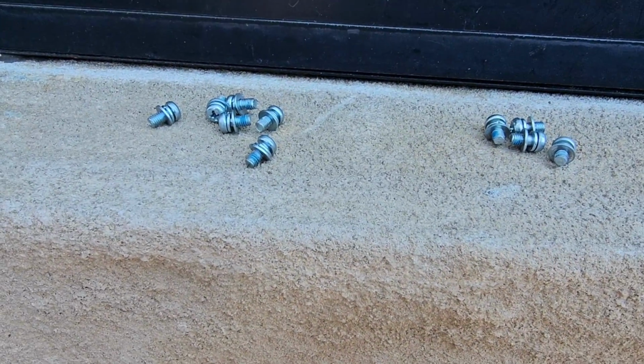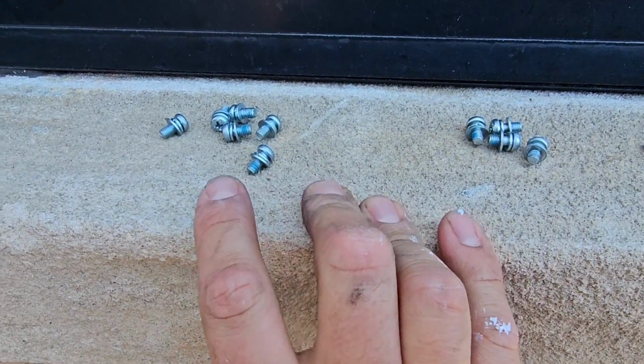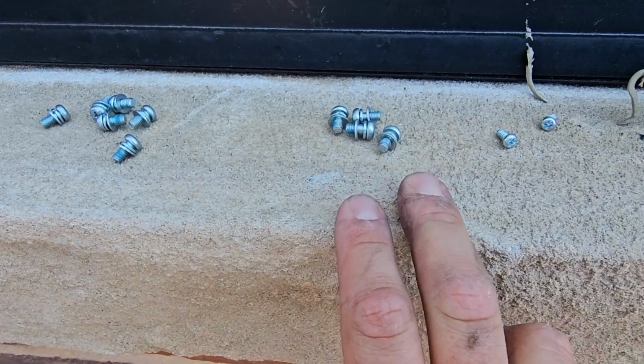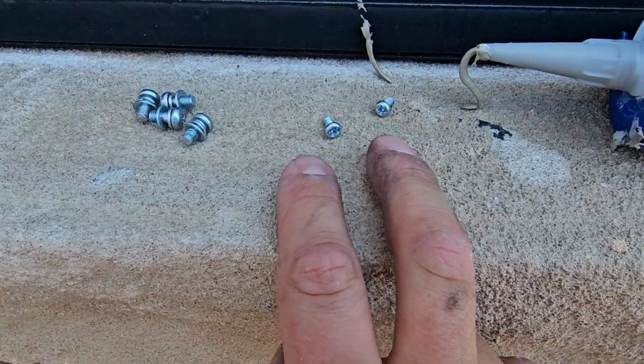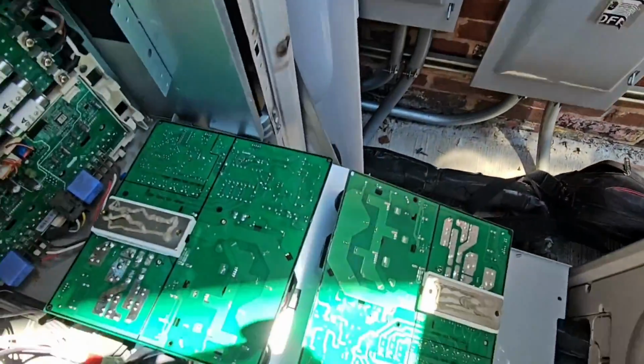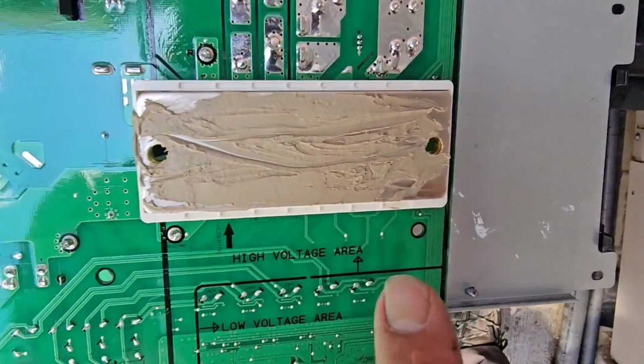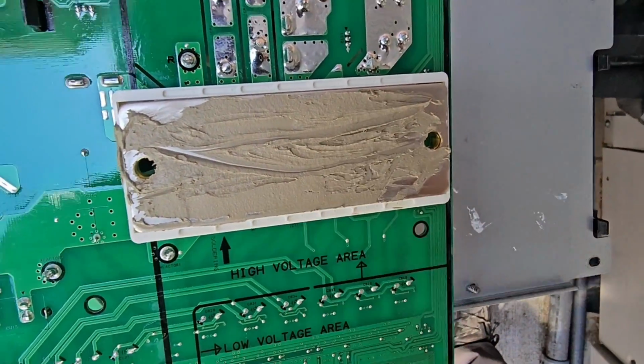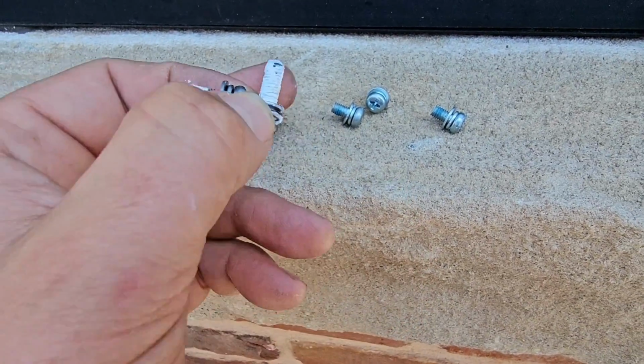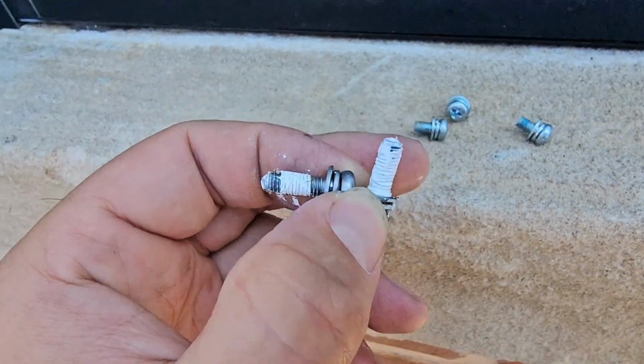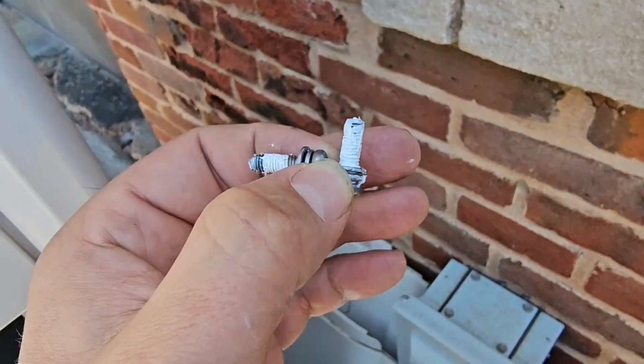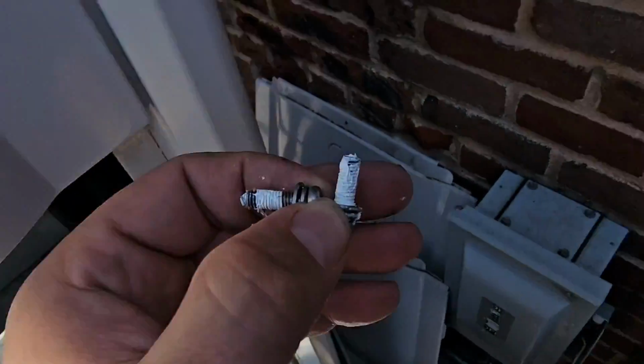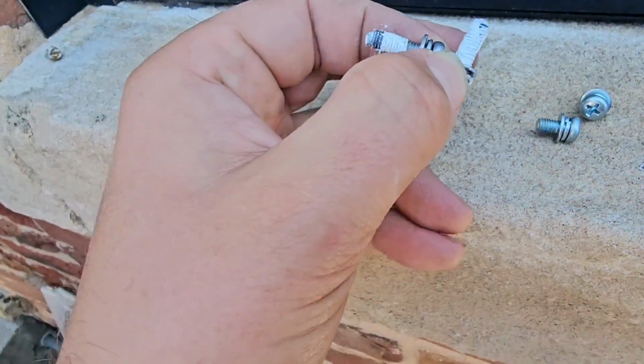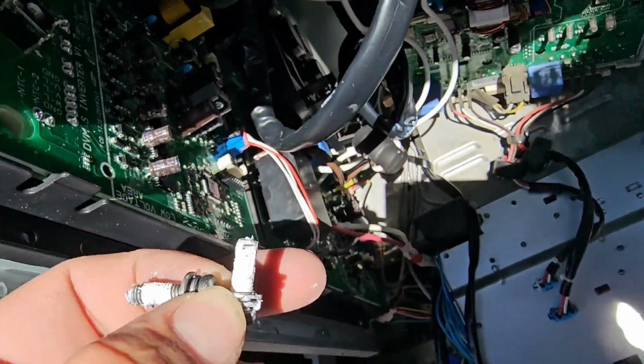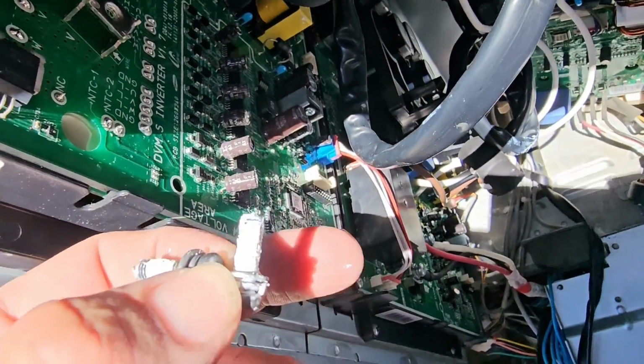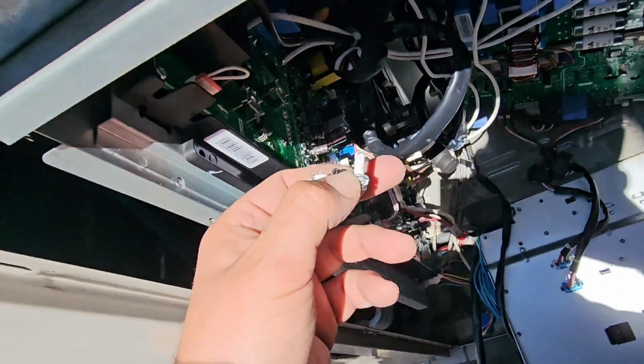Here were the screws that hold the wires for the reactor and the wires to the compressor on the inverter board, and there's the two screws for the inverter board. I'm almost done smoothing it out. You're not going to see any of that metal when I finish. There's a difference between the screws that hold the wires to the inverter board and the screws that hold the inverter board to the heatsink. These screws are much longer, so make sure you don't mix up the screws, and make sure you don't over tighten these. You do not want to crack the inverter board, okay?